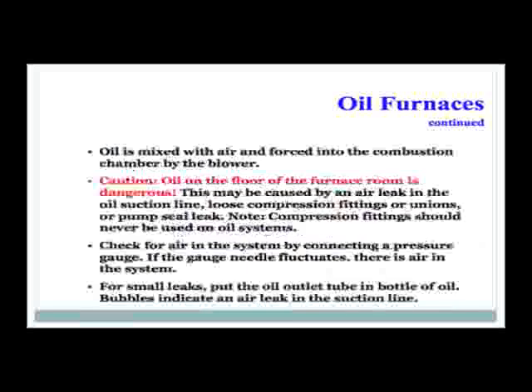Oil is mixed with air and forced into the combustion chamber by the blower and burner motor. Oil on the floor of the furnace room is dangerous and could be caused by an air leak in the oil suction line, loose compression fittings, or unions or pump seals. Compression fittings should never be used on an oil system. Check for air in the system by connecting a pressure gauge — if the gauge needle fluctuates, there is air in the system. For small leaks, put the oil outlet tube in a bottle of oil; bubbles indicate an air leak on the suction line.